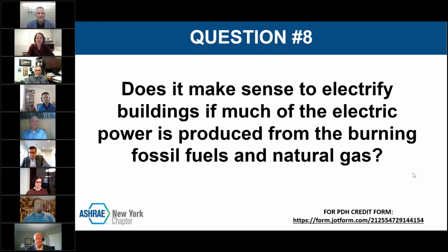It goes back to my comments earlier that some of it is how you manage and balance those loads. My all-electric house has very low demand. Why? My heat pumps are tiny. Part of that's efficiency, part of that's storage in terms of hot water. The end result is my heat pump never draws more than 1600 watts to heat and cool my whole house. That's a design piece of it and how you put those together. Where you get into trouble around peak demand is saying things like, well, we don't really believe in this heat pump, therefore we're going to put in electric resistance backup everywhere. That is problematic from a design point of view.